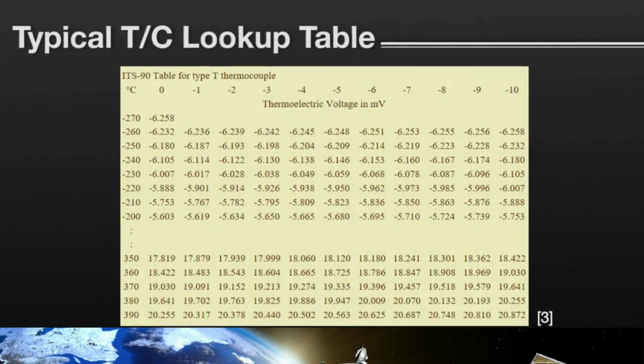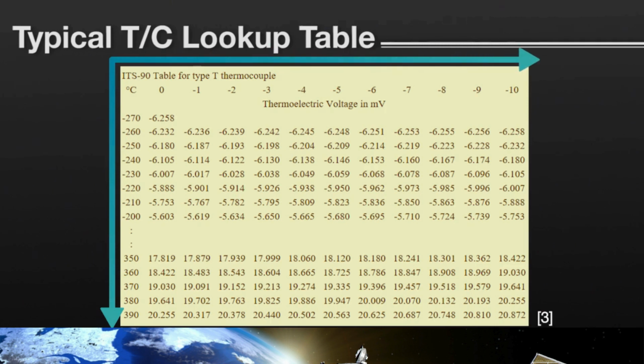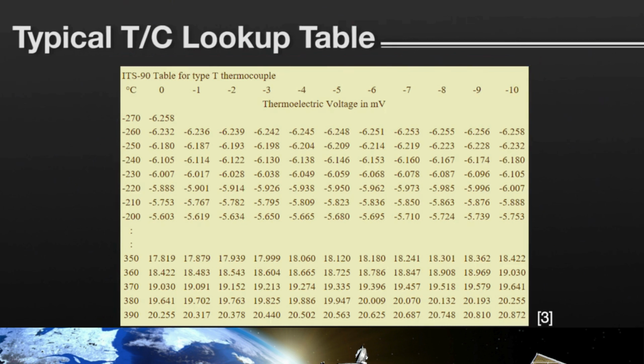Here's an excerpt from the table ITS-90, the thermoelectric voltage table. In this case, it shows type T voltage data. You read the temperature on the left column in 10 degrees C intervals, then you read across the top row to find your reading to the nearest 1 degree. You intersect the row and the column, and you find the thermoelectric reading in millivolts.